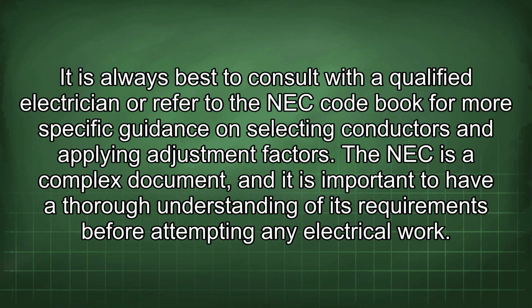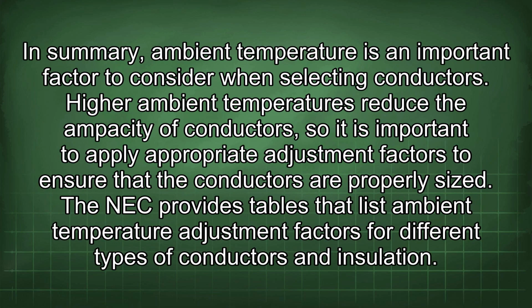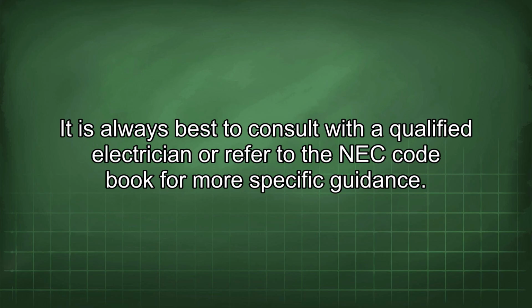The NEC is a complex document, and it is important to have a thorough understanding of its requirements before attempting any electrical work. In summary, ambient temperature is an important factor to consider when selecting conductors. Higher ambient temperatures reduce the ampacity of conductors, so it is important to apply appropriate adjustment factors to ensure that the conductors are properly sized. The NEC provides tables that list ambient temperature adjustment factors for different types of conductors and insulation. It is always best to consult with a qualified electrician or refer to the NEC code book for more specific guidance.